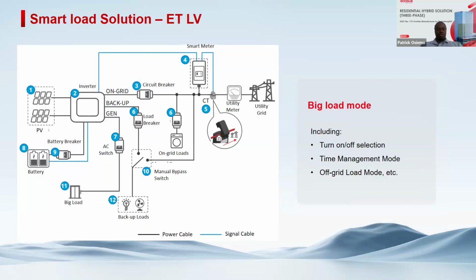Another feature is the smart load control. Now, the same diesel generator port, apart from being connected to a diesel generator, apart from being connected to an on-grid inverter, the same port can still be configured to be an output to some certain big loads. Now, these certain big loads are the ones which can, let's say, surge, or you do not want them to drain your batteries too much, such that if you're still working off-grid, and you do not want to consume your batteries too much with the big loads, then the inverter has a smart way in which you can configure it, in the sense that it can switch off or disconnect power to the big loads that are connected to the generator port and allow only the essential loads to be draining your battery. So there are various flexible ways in which you can use the same diesel generator port: connecting a big load, connecting a diesel generator, as well as connecting a grid-tied inverter to it.